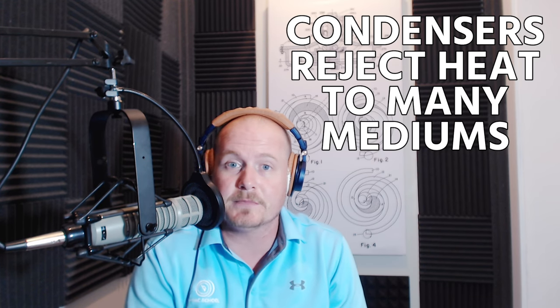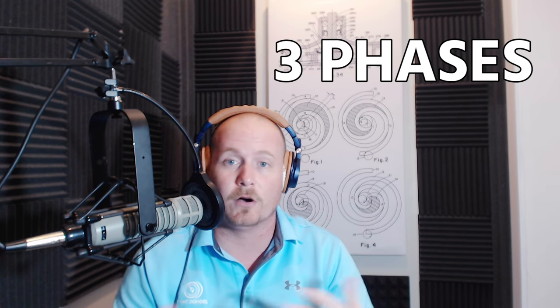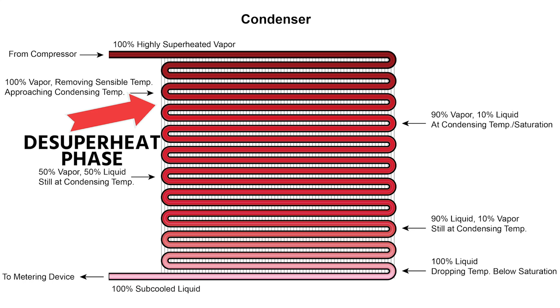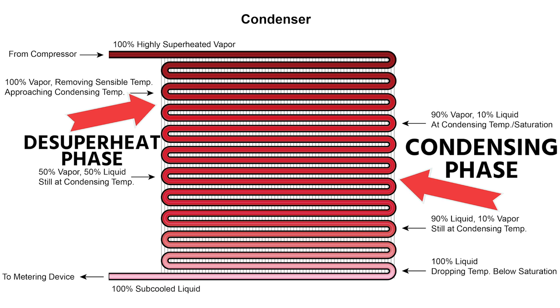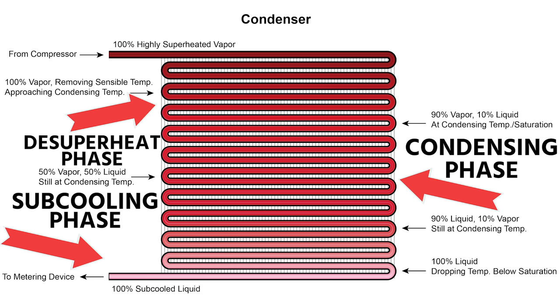Condensers can reject heat to many different types of mediums, but they are all heat rejecters and they all go through three phases: the desuperheating phase brings the refrigerant to the condensing temperature in that first portion at the top; the condensing phase runs through the bulk of the condenser; and the sub-cooling phase at the end drops the temperature below the saturation temperature. You can only have sub-cooling once the refrigerant is fully liquid, and you can only have superheat if it is fully vapor. It's like watching a boiling pot of water in reverse — changing from vapor to liquid instead of liquid to vapor. That's your condenser, the heat rejecter.